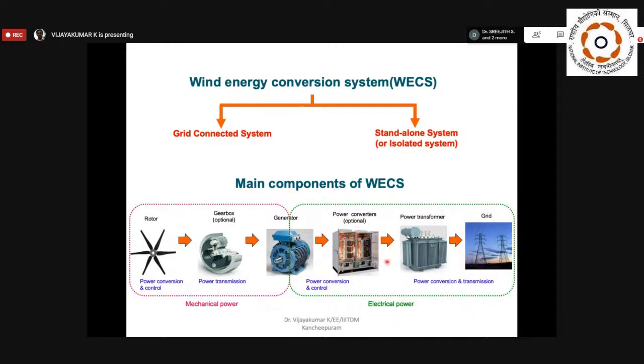Then the power transformers. What's the purpose of power transformers here? You just have to match the grid voltage and your wind turbine voltage. Maybe I can say in the primary distribution network, the voltage is 11 kV. My wind turbine power output is at 440 volts. Then you have to match the 440 volts with the 11 kV of the grid. So for that purpose, they may use the power transformers in between.